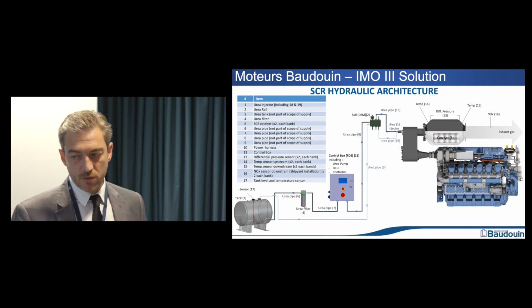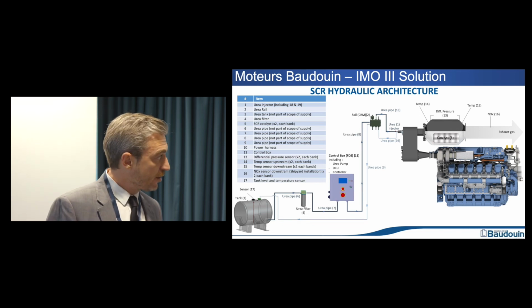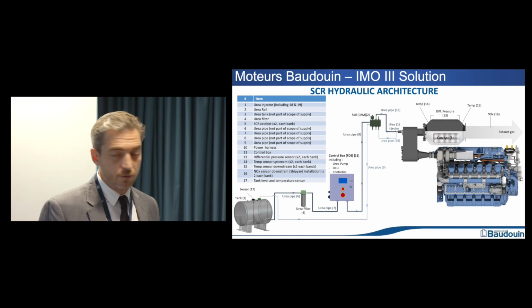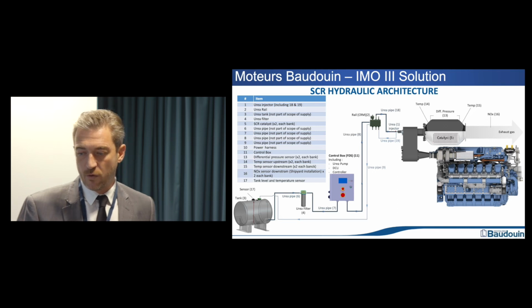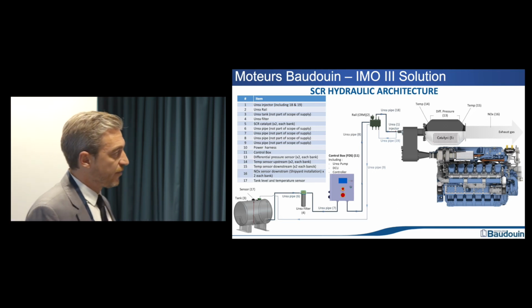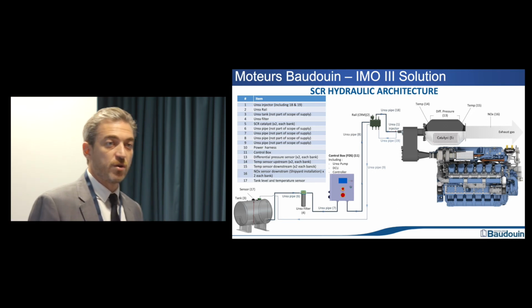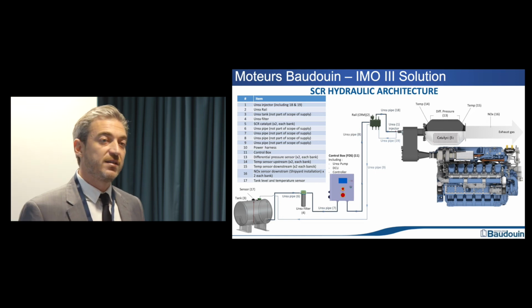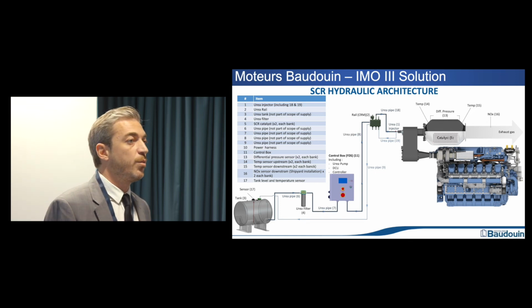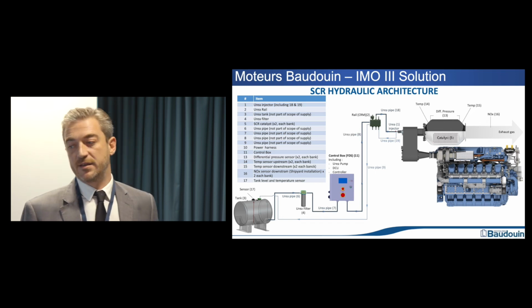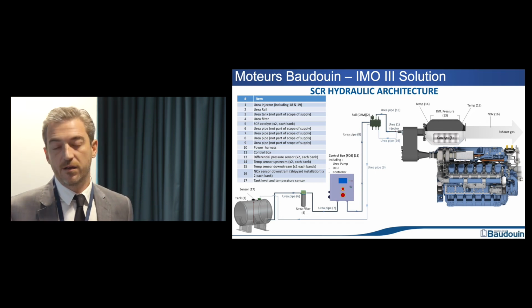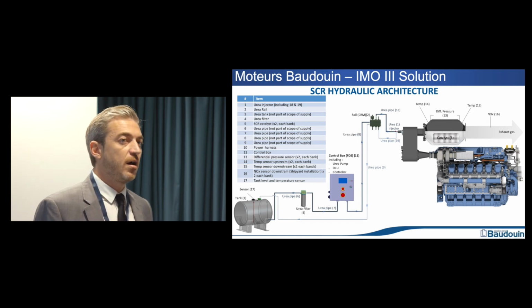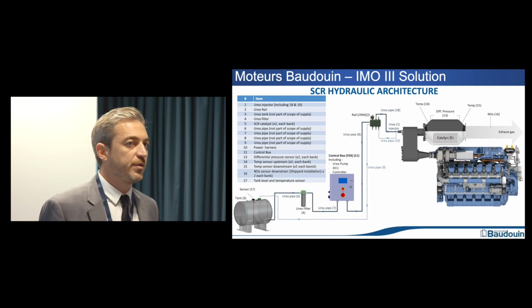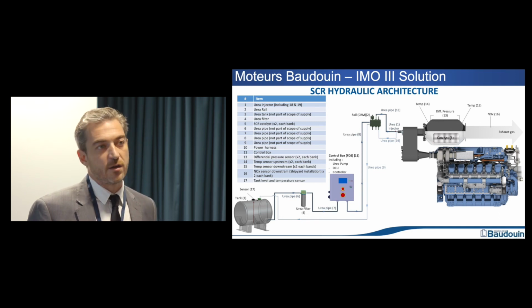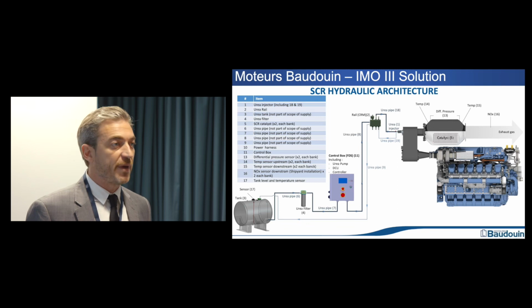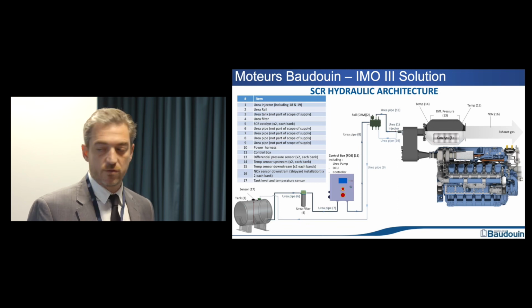That dosing module injects the urea, the ammonia, into the exhaust. As said previously, we have a temperature sensor. We need to ensure we activate the SCR only when above 200 degrees, and monitor temperature because above 550-600 degrees the SCR will be damaged by too hot exhaust.